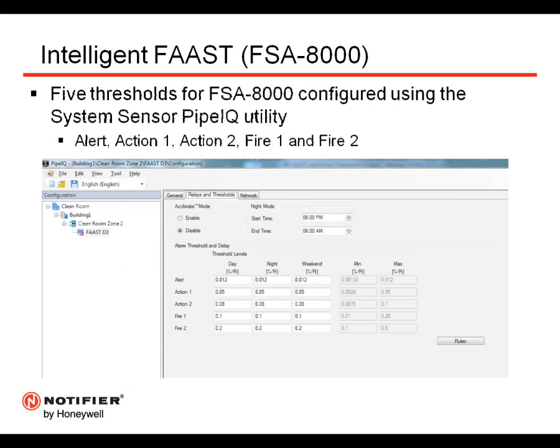Just a little bit on the configuration. There are 5 thresholds or kind of sensitivity levels that can be set for the FSA 8000 configured using the system sensor Pipe IQ utility. It's the same Pipe IQ utility that is used to configure the conventional FAAST unit. So it has up to those five thresholds: alert, action one, action two, fire one, and fire two. And each one can be set to a different sensitivity level. So it truly is combining five addresses or five detectors into one in that intelligent FAAST unit, and we can program different type codes or different type IDs associated with the five thresholds that have been set using Pipe IQ.